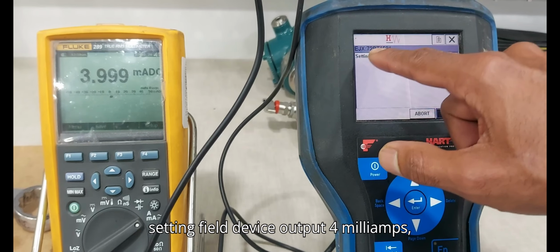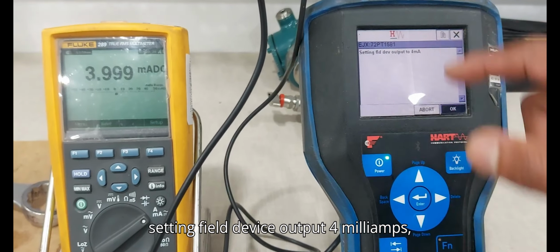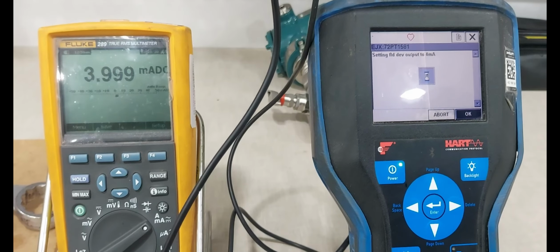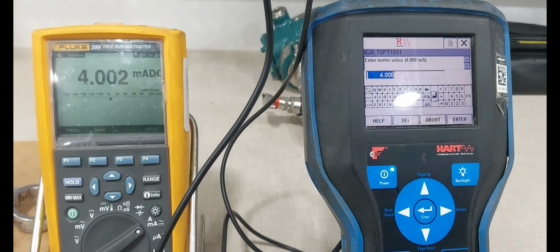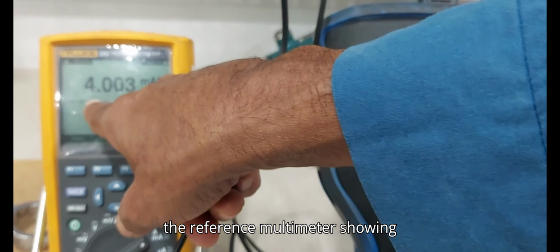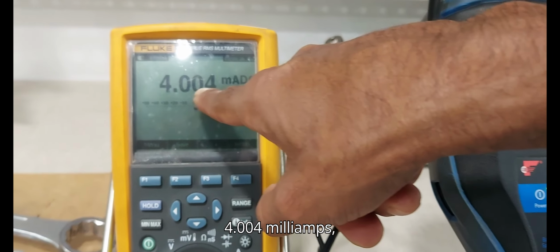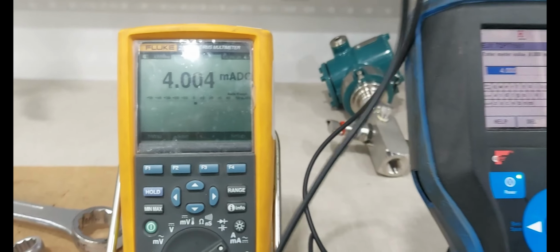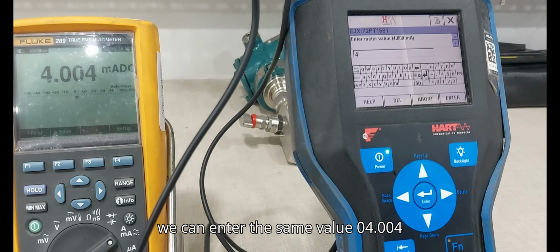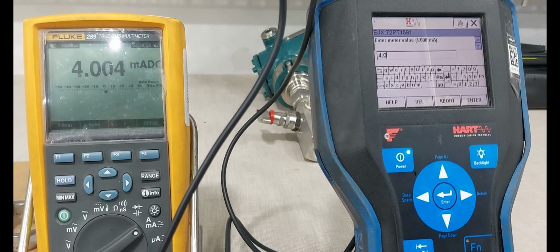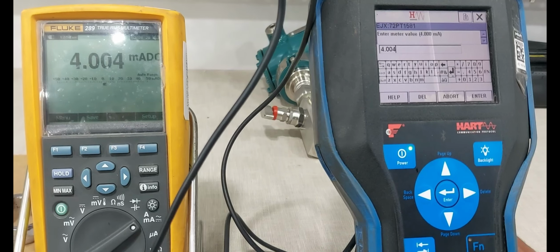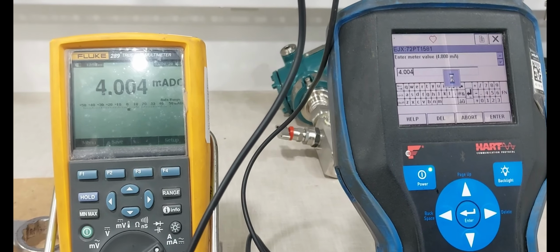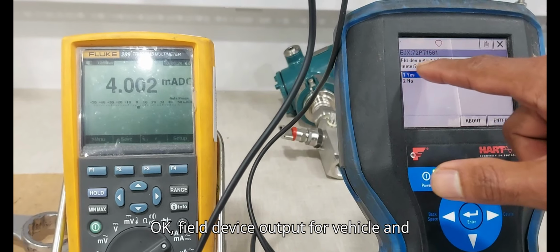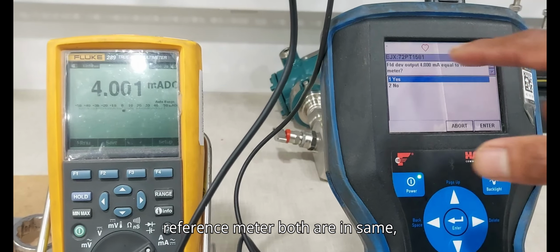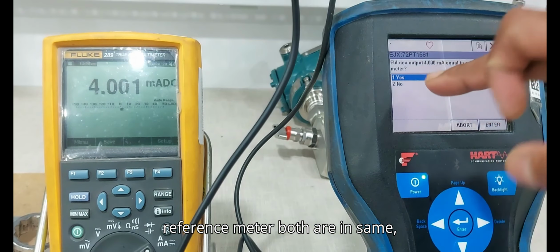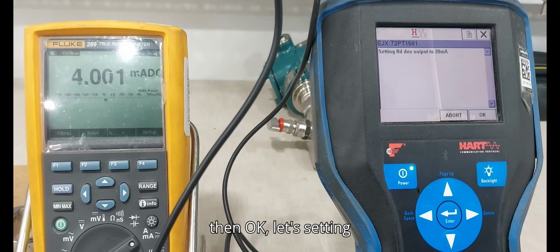Next, setting field device output 4 milliamps. Then OK. The reference multimeter shows 4.004 milliamps. We can enter the same value, 4.004 milliamps. Enter. Okay, field device output 4 equals the reference meter. Both are the same. Then OK.